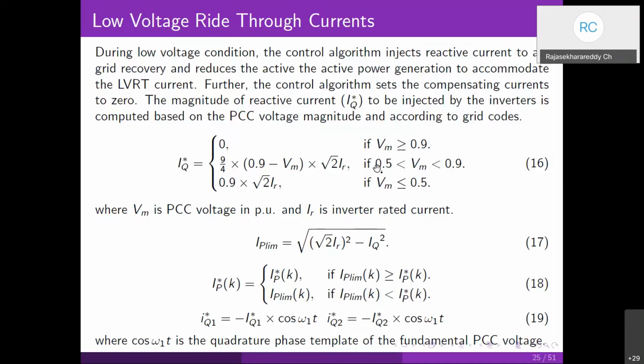If the grid voltage magnitude lies between 0.5 and 0.9, this is the expression we use to estimate IQ, the reactive current to be injected by the voltage source inverter. If the grid voltage magnitude is less than 0.5, we go for this expression for calculating the reactive current magnitude. Here Vm is the PCC voltage magnitude in per unit, and IR is the rated inverter current.